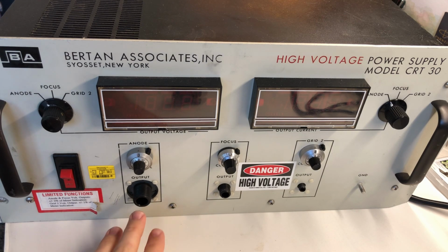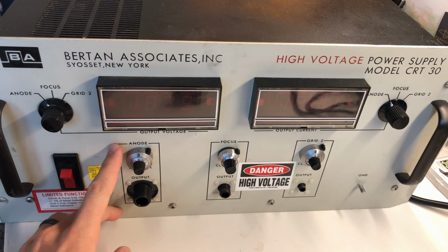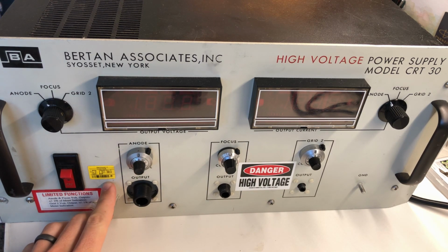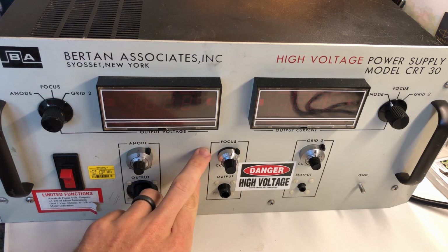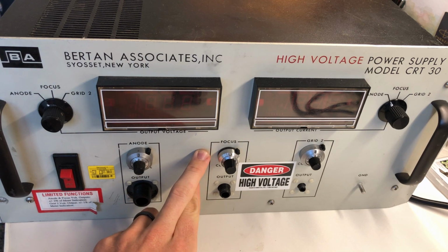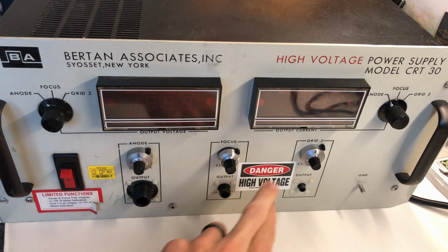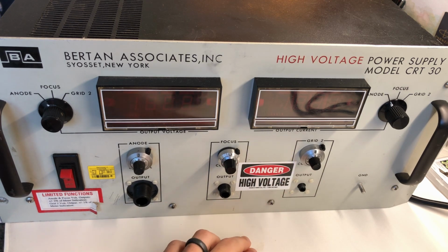This model actually has 3 outputs, as you can see here. This main anode output can go up to 30 kV at 2 milliamps. This focus output can go up to 8 kV at 1 milliamp, and the grid 2 output can go up to 1 kV at 1 milliamp.